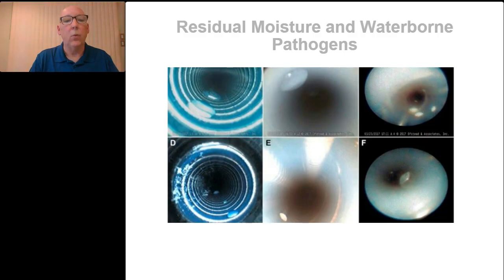And here you see on the screen what it looks like when there is residual moisture and potential waterborne pathogens present inside a lumen. Bacteria can be attached to those droplets of moisture that settle on the interior surface of a lumen device. So let's talk about what we've learned so far relative to this lumen device. How do we apply those 4 principles? Can you air dry a lumen? Well, since lumens are interior surfaces, that won't work very well, will it? Simply setting devices aside and thinking that they will dry on their own with air drying within a reasonable time frame won't work too well for your processes. It may take a long time.